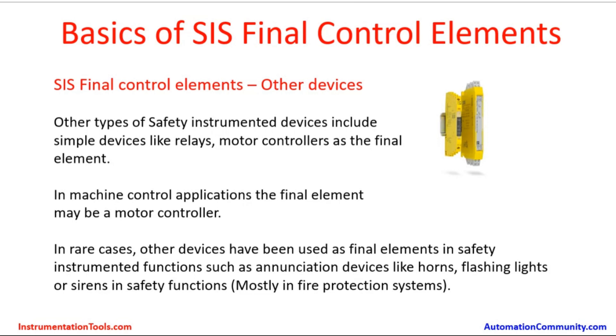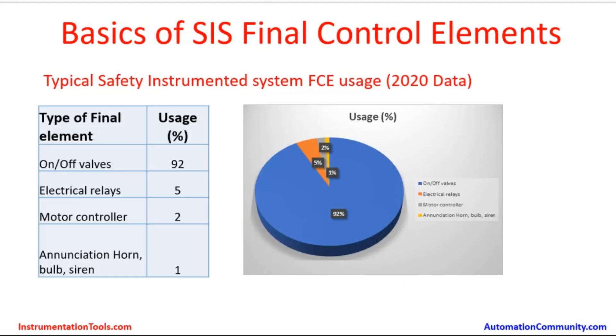There are other devices used as SIS final control elements. Other types of safety instrumented system devices include simple devices like relays and motor controllers as final elements in machine control applications. In rare cases, other devices have been used as final elements in safety instrumented functions, such as annunciation devices like horns, flashing lights, or sirens. Most of these will be in fire protection systems, using a simple relay which gets power from the digital output module of the safety instrumented system.